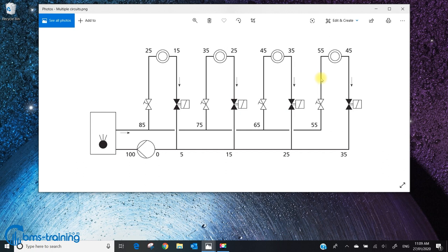Now, I was trying to do this to try and get slightly closer to what's reasonable, but in actual fact, that's still an estimation and still not right, because depending on how far you are from the plant room, or really how close you are to the plant room, it just gets worse and worse. So I'm not saying that you guys should go away now and start sizing valves differently. You need to follow the methodology of your company. But I want you to think about the fact that what you're doing is actually wrong and understand this when you're sizing valves.